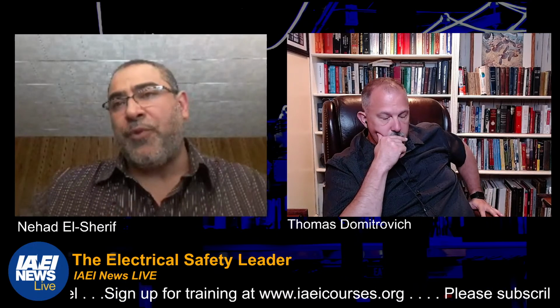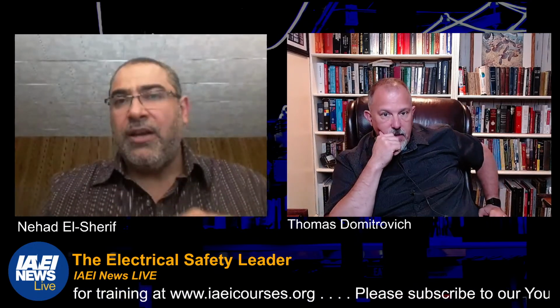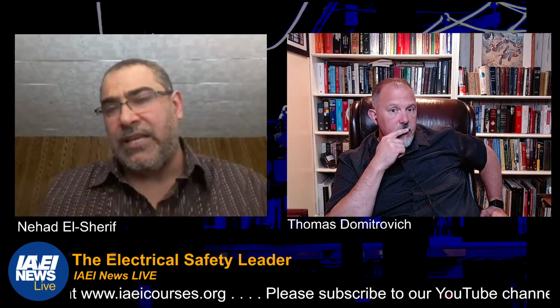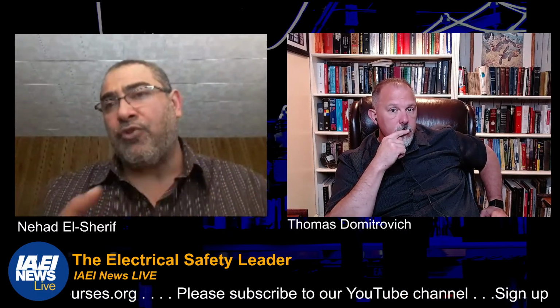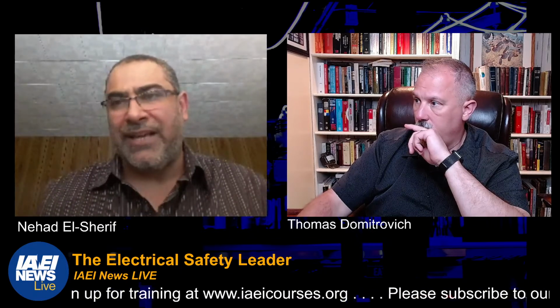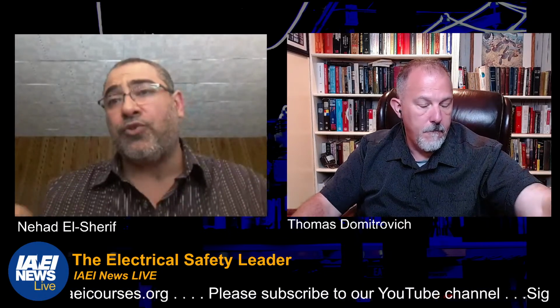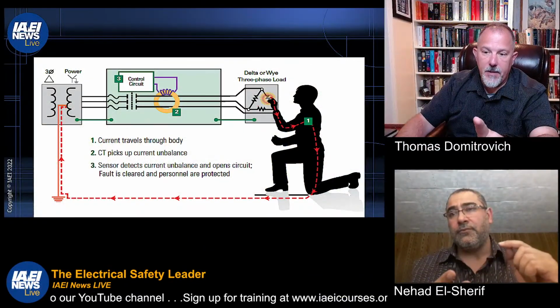So what this means, reliable grounding, is the special purpose GFCIs have an extra layer of protection, and this requires Class C, D, and E to monitor your equipment grounding conductor or the grounding connection of the equipment that you're protecting. And if there's a problem in your grounding circuit, aka your equipment grounding conductor is severed, not connected, or the impedance is much higher than expected for whatever reason, the special purpose GFCI is required to trip. So it doesn't only trip because of the leakage current, it's now required to trip if there is any grounding problem. And I just want to make sure that's an important piece.